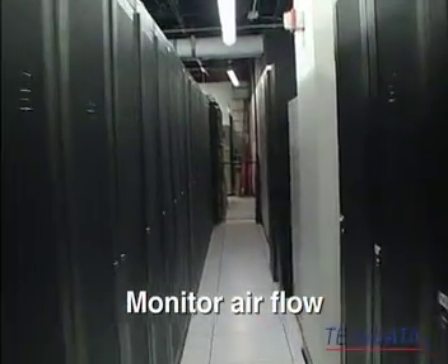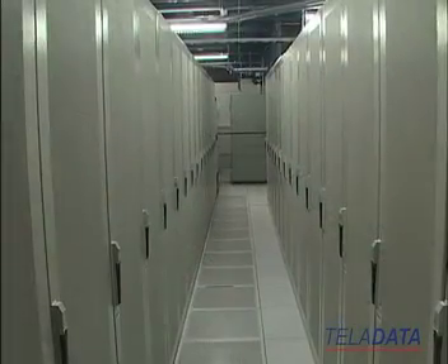Another thing you can do is you can look at the airflow in your facility. And in a lot of these facilities, you have hot spots, you have cold spots, but you're not delivering the cool air to the places that need to get it as accurately and as cheaply as you could. And simply by looking again at what's going on in your facility, there's ways you can change the operations that don't cost a lot in capital. Typical data centers can save 10 to 30% pretty easily. We're seeing that facilities and IT are doing a better job of communicating with each other, but they're still speaking different languages, right? And so is there another new language to learn for these guys to communicate?